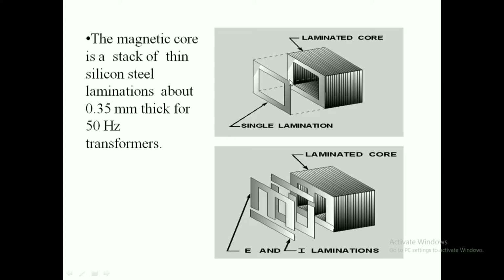As we know, there are two types of losses in a transformer. One is hysteresis loss and the other one is eddy current loss. We generally use CRGO steel to make these thin laminations because if we use CRGO steel, then the permeability of the core will be increased, so more flux will be confined in this core. So as the permeability increases, the hysteresis loss will be decreased.